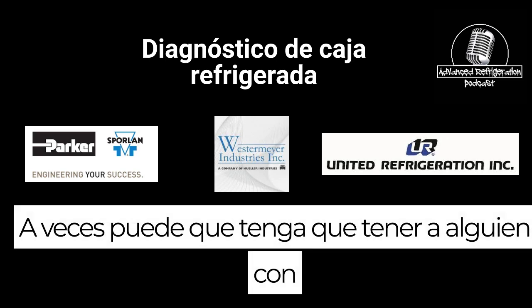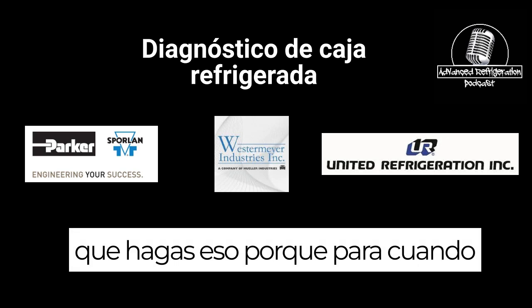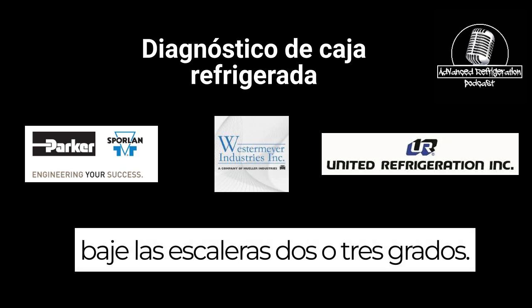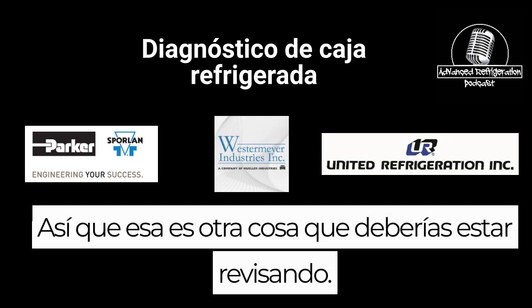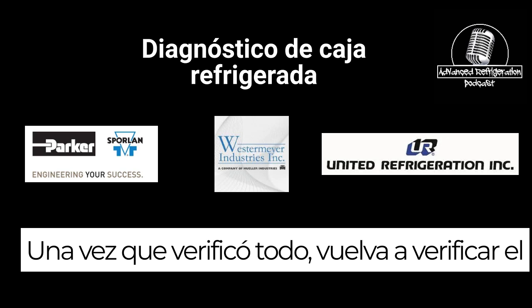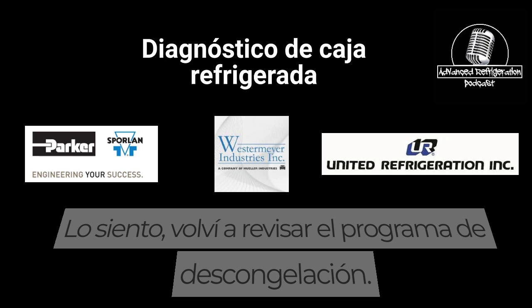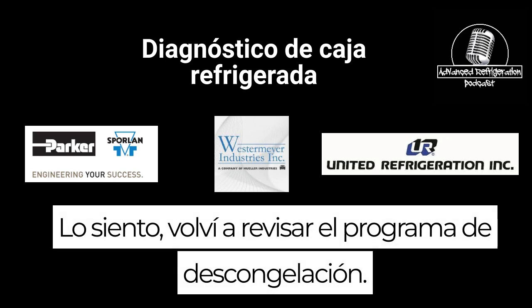Sometimes you might have to have someone with you to do that, because by the time you walk downstairs it could be off by 2 or 3 degrees. So that's another thing you should be checking once you've verified everything. Back to checking the defrost schedule.